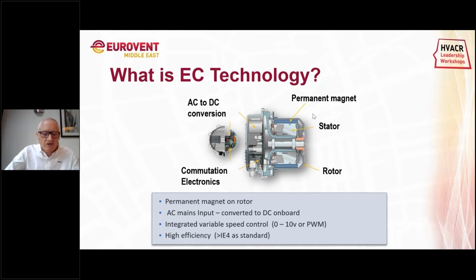This is only half the story. The use of modern electronics in controlling the motor has opened up many possibilities for reducing the power. The control options - this is the electronics built into the back of the motor - we can control an EC fan very accurately and efficiently using the integrated circuitry. One of the biggest factors is speed control, and the actual control functions itself.